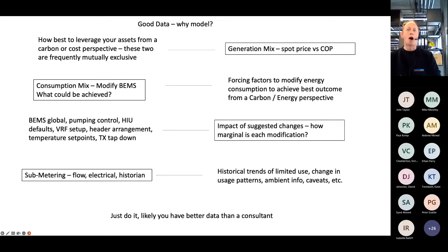If you can get that back onto a constant temperature variable flow system, that's one of the best indicators you can have of how a building's operating. It's a real indicator of how much bypass you're getting, either via the fan coils or air handling, or via the over temperature bypass, and that leads to inefficient pumping, failed valves.